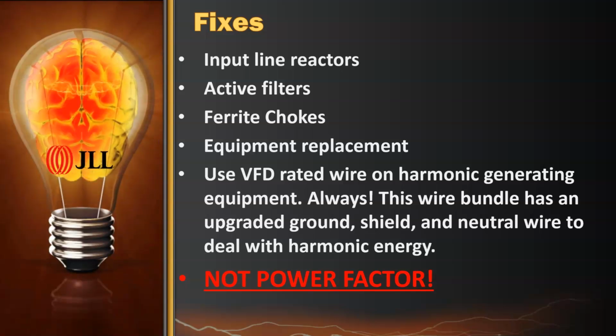And one of the things about a harmonic is that if it's present in the wire, it creates a stronger magnetic field. If you can affect that magnetic field, you will basically reduce the harmonic. You'll convert that harmonic energy into heat, and that's what an input line reactor does. It reduces that magnetic field to a point that it's normal for a 60 hertz signal, and when it reduces it, it converts that energy into heat.